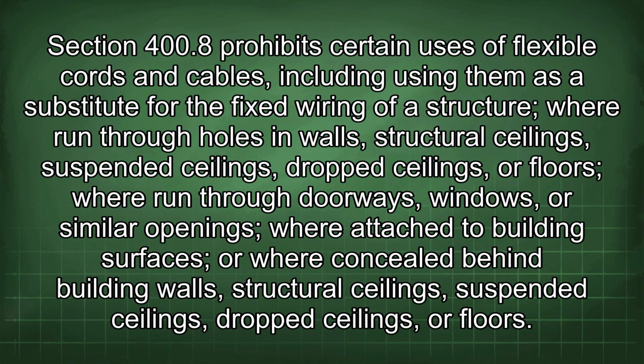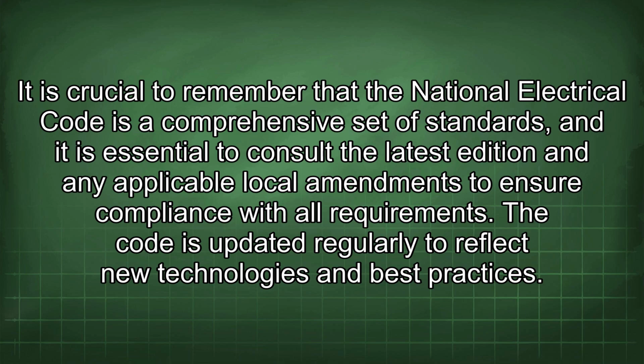Section 400.8 prohibits certain uses of flexible cords and cables, including using them as a substitute for the fixed wiring of a structure, where run through holes in walls, structural ceilings, suspended ceilings, dropped ceilings, or floors, where run through doorways, windows, or similar openings, where attached to building surfaces, or where concealed behind building walls, structural ceilings, suspended ceilings, drop ceilings, or floors. It is crucial to remember that the National Electrical Code is a comprehensive set of standards, and it is essential to consult the latest edition and any applicable local amendments to ensure compliance with all requirements. The code is updated regularly to reflect new technologies and best practices.